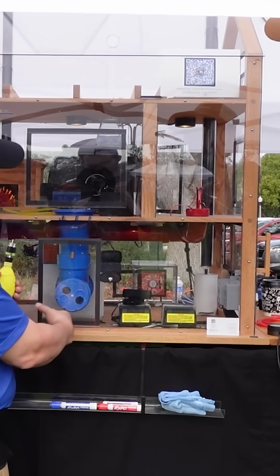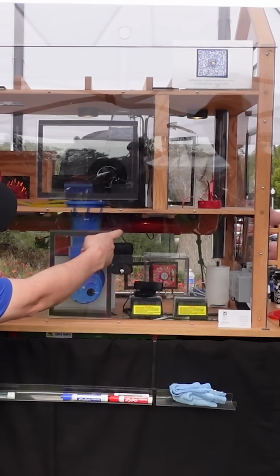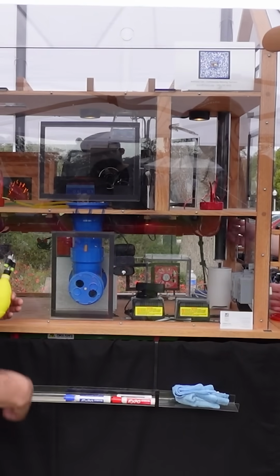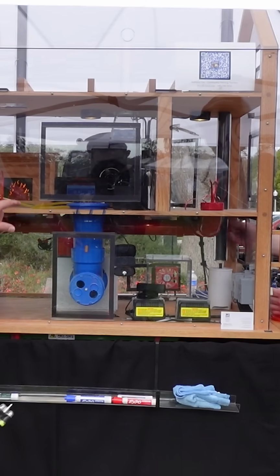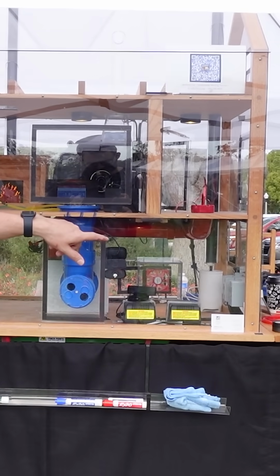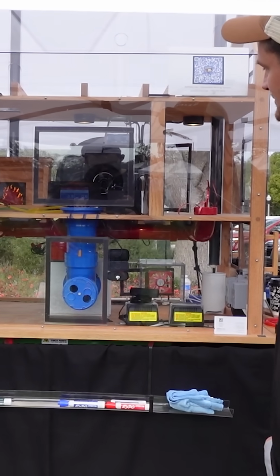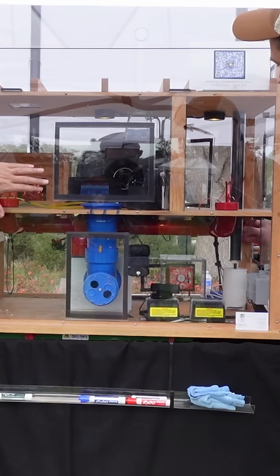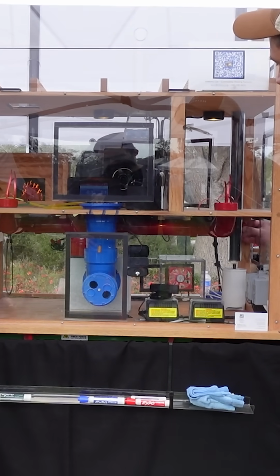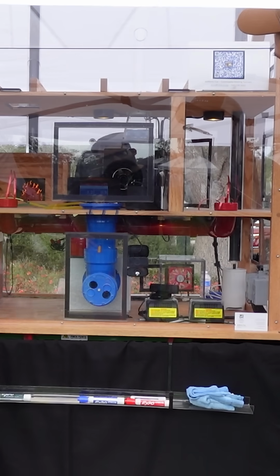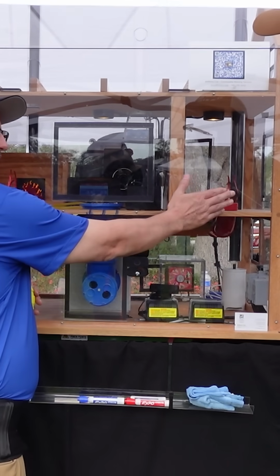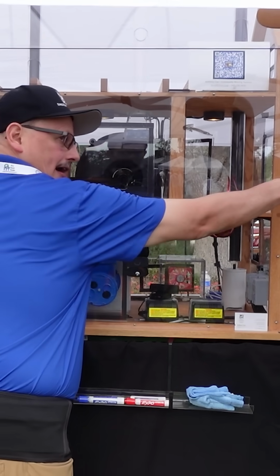But if I make a leak in the ductwork, like the red supply duct down there — you can see where he takes the duct off — now you can see the pressure kind of equalizes out. Now when he removes that, some of the supply air that was blowing out here is now blowing out the leak instead.